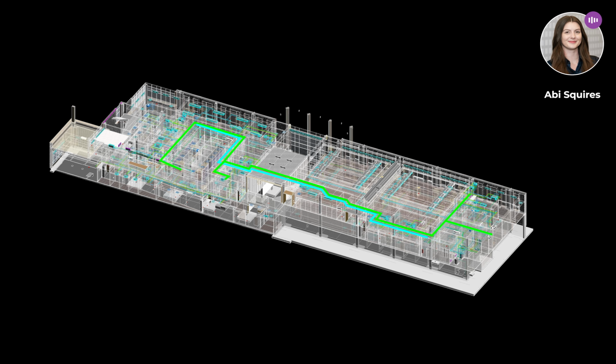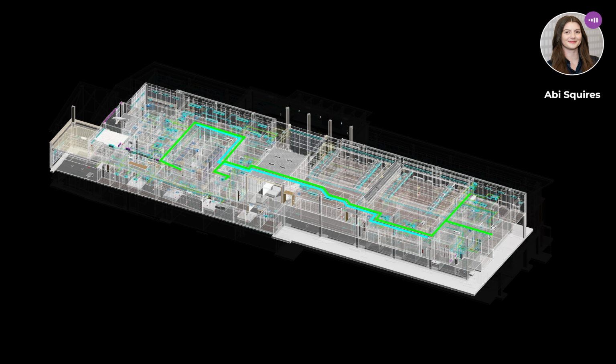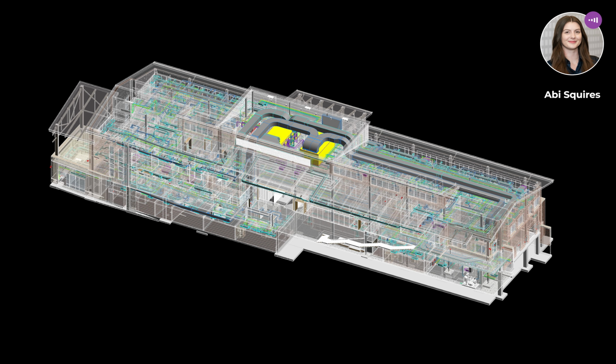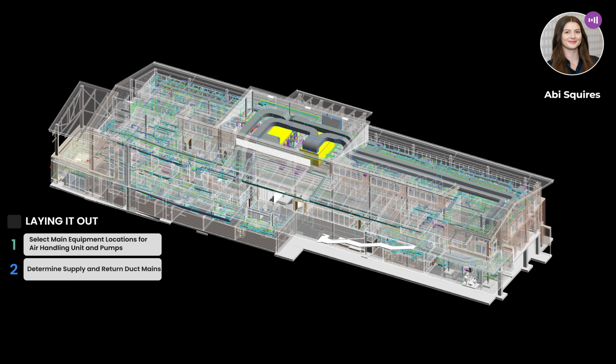Chilled beams and cooling panels aid in increasing energy efficiency in the building. It is important to remember that this water piping system aids in conditioning the space and is separate from water provided to plumbing fixtures. These elements are the basics for laying out a mechanical system in your building. To review the steps for laying it out, first, select main equipment locations for air handling units and pumps. Second, determine supply duct mains, and then the return duct mains or exhaust duct mains. And then consider sustainability strategies.